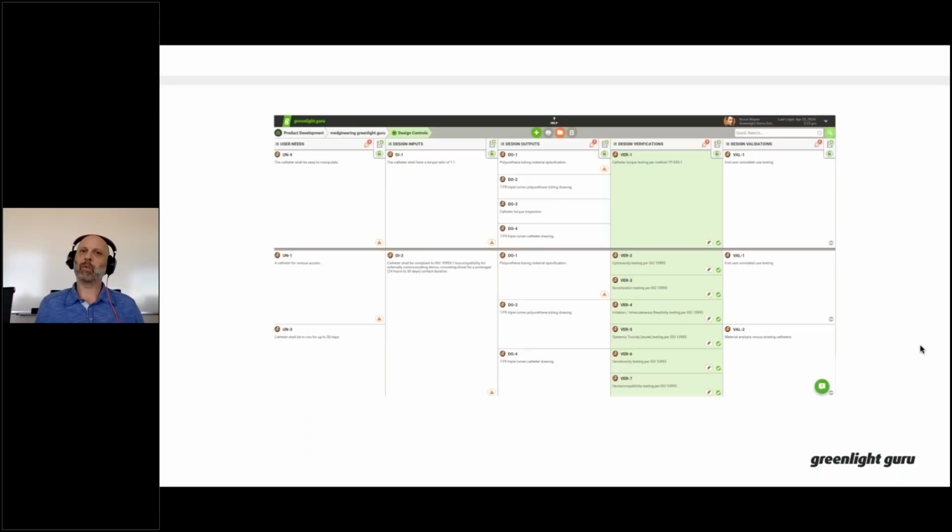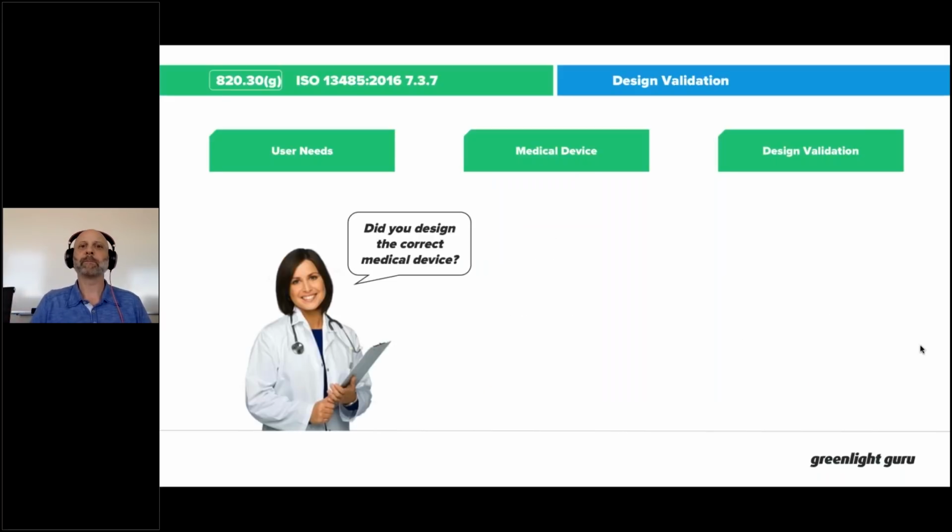Traceability, it's probably the sixth time that I've mentioned that, but traceability is very important when it comes to verification and validation, because we need to show how that thread flows throughout the entire design and development process. We need to show that connectivity. And verification is one of those confirmation points in time during the design and development where I'm tying design inputs and design outputs together. And then I'm going to talk about validation, kind of tying it all together at the tail end. But I need to be able to show and demonstrate traceability.